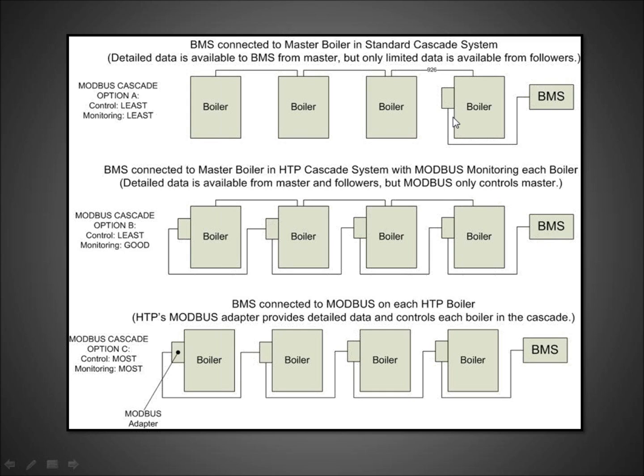Right, that's right. The building management system on the second example here, which is option B, we can control least, where monitoring is good. In other words, we can monitor all the connected boilers, but the control is coming from our controller. All the building management system is doing is really monitoring what each connected boiler is doing as far as its individual faults and its individual fan speeds, what its supply and return rate is, what its firing rate is. So the detailed data is available from the master and the followers, but ModBus only controls the master. So our control is controlling this bank of boilers based on our standard product cascade programming, and then the building management system is getting more information than what we saw up here because we've got ModBus adapters on each one.